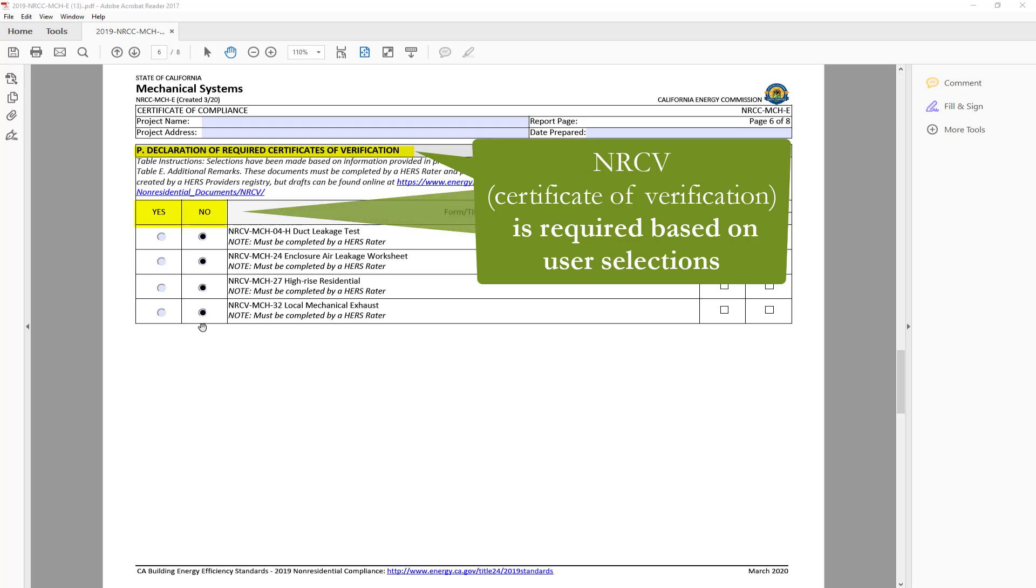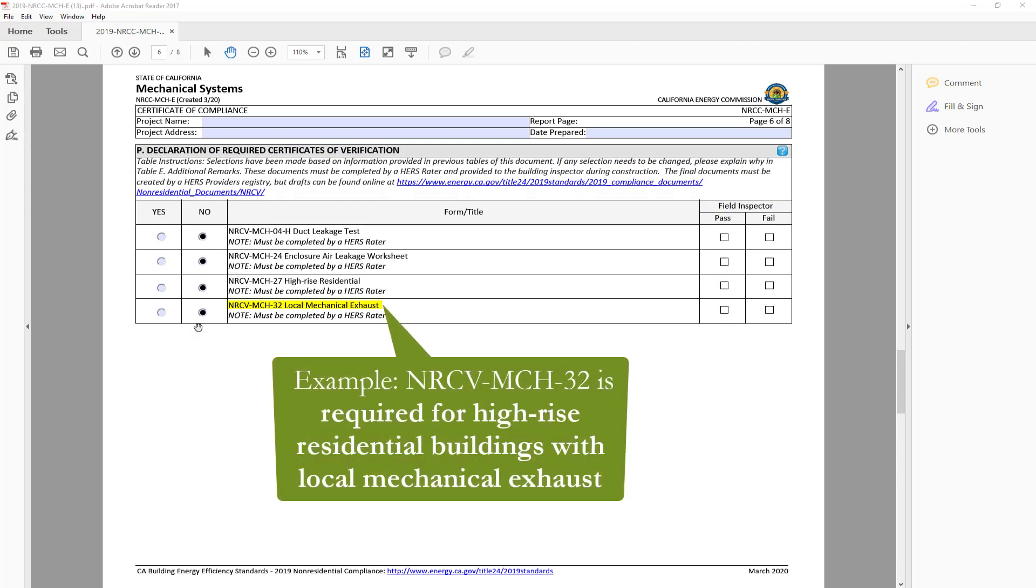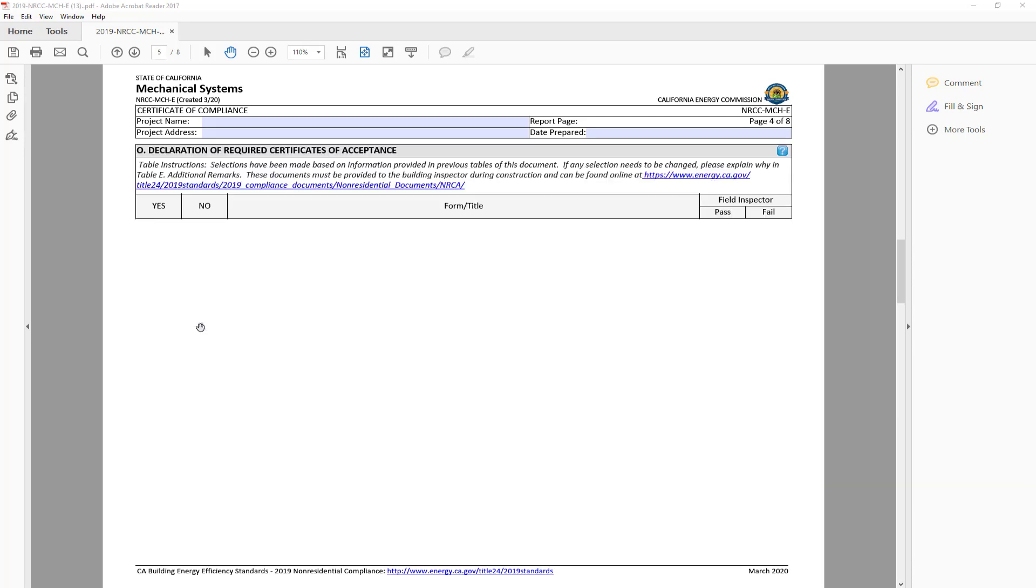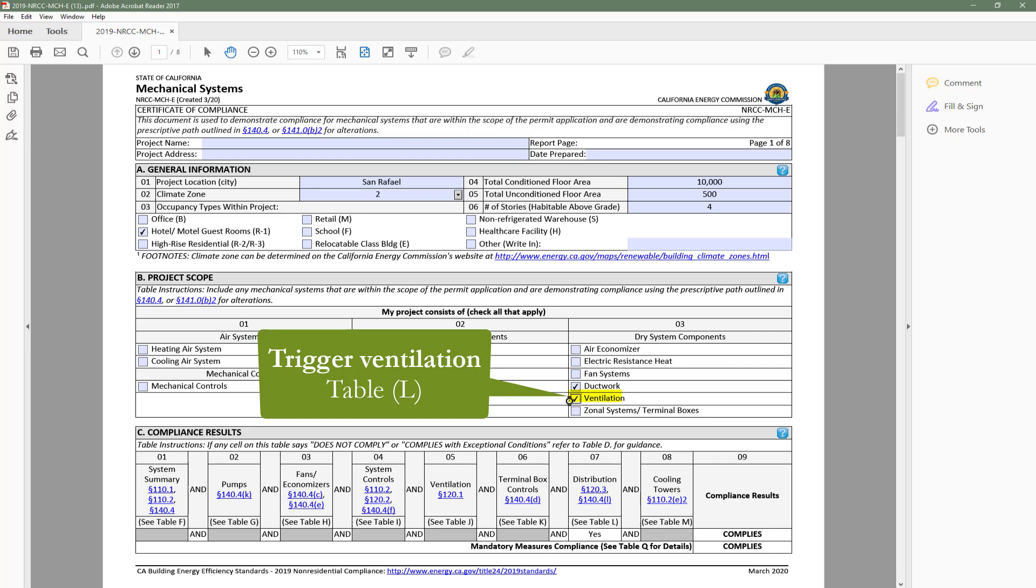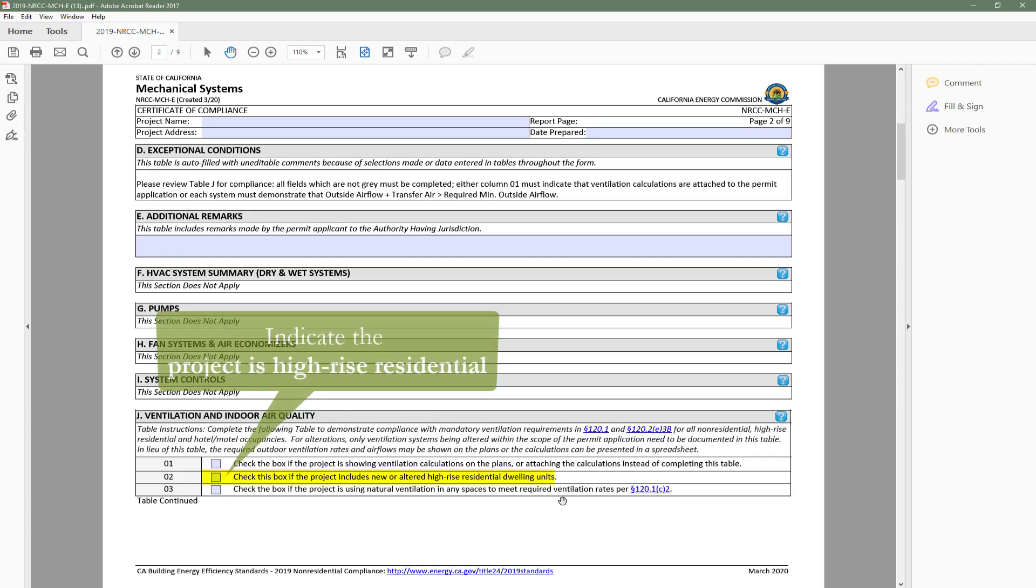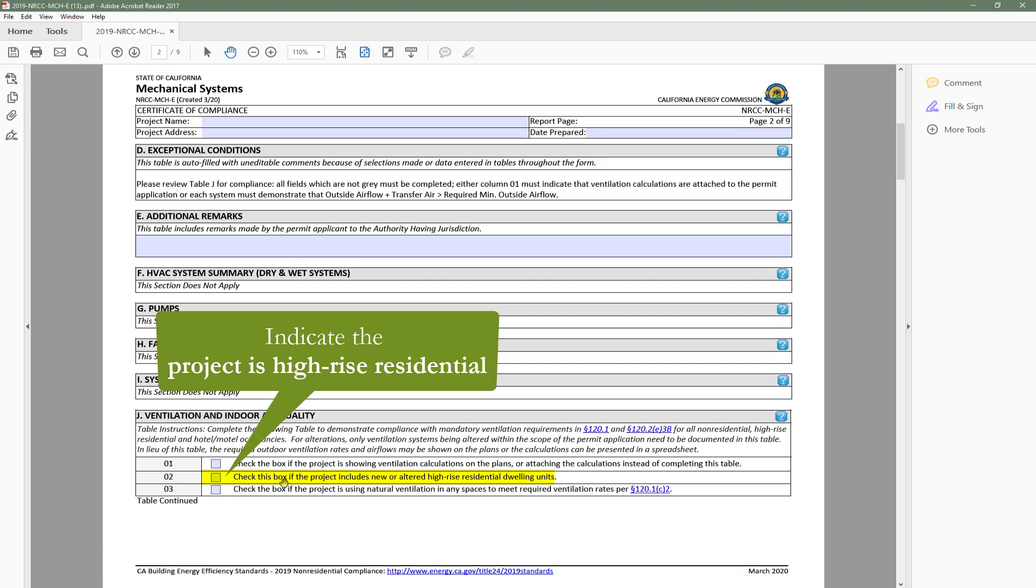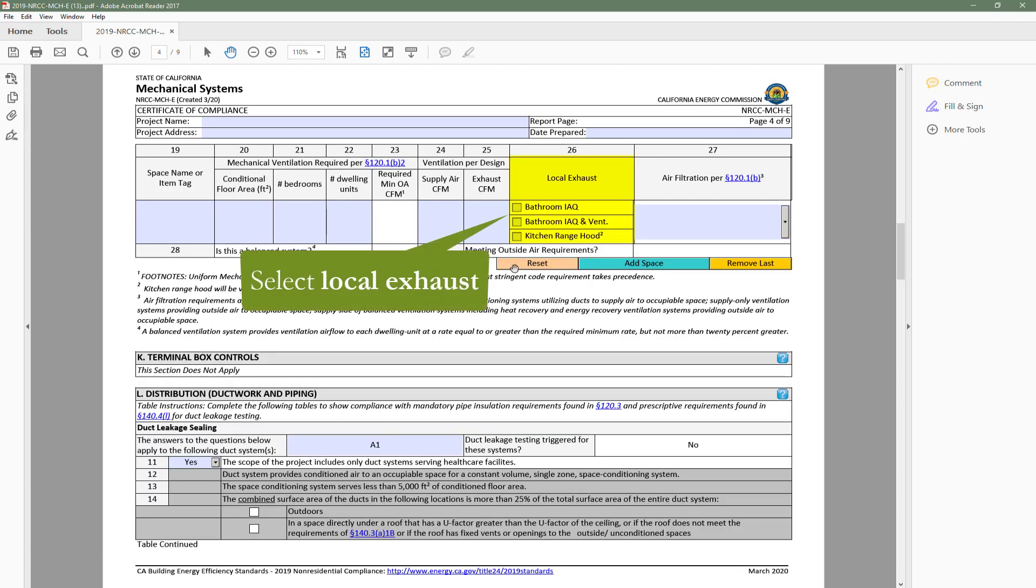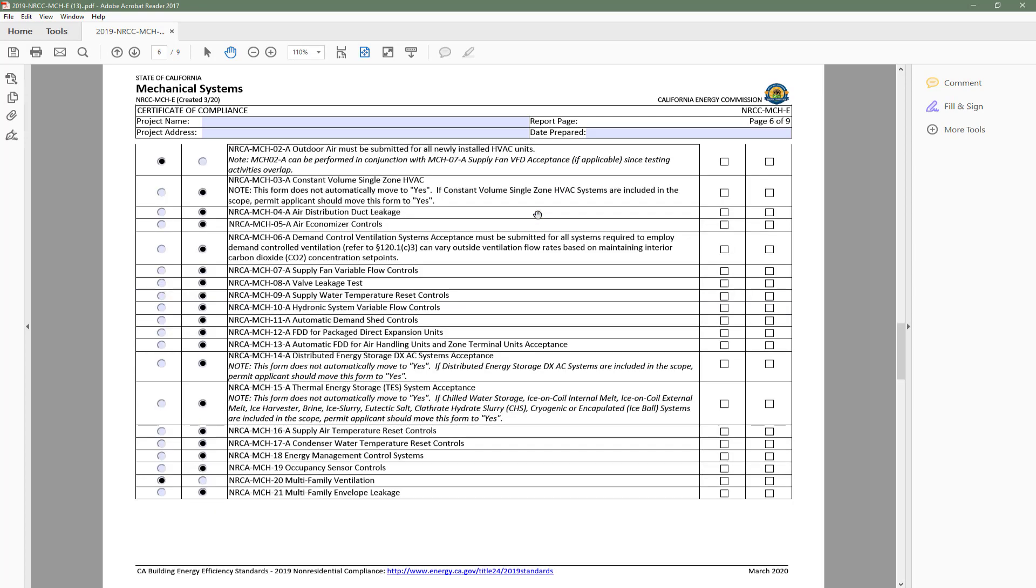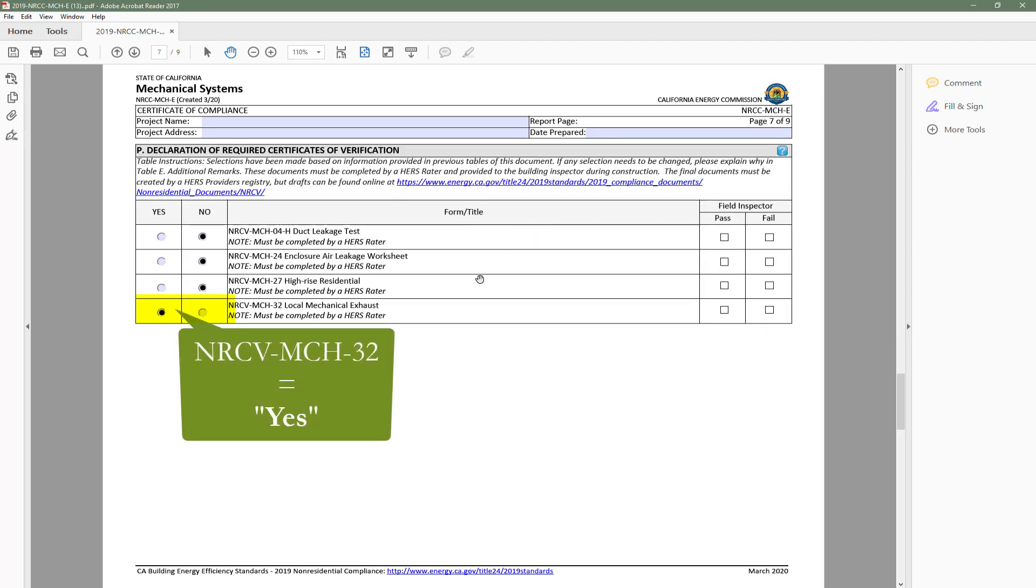For example, the NRCV Mech 32 is required for high-rise residential projects that include local mechanical exhaust. So if we go ahead and trigger the Ventilation Table, indicate that the project is a high-rise residential project, and select one of three local exhaust types, the NRCV Mech 32 now indicates Yes for the building inspector.